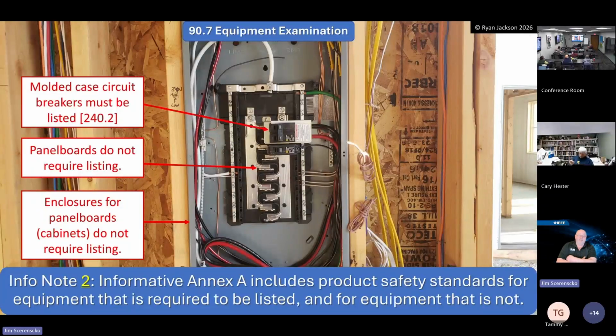And that's a really sore subject because when I did the Falcon Stadium in Atlanta, I was the quality control, quality assurance manager for that building when it was built from the dirt up. The engineers came back and said, well, we don't want to see any of the labels from the EMT. Well, it's an open floor plan building. I mean, you're going to see the conduit. And every stick of conduit has a label on it. It's not only the listing, but it's also the SKU number and the barcode and everything else, because they do sell it a stick at a time in some places. And so they wanted us to go back and peel off all the labels. I said, I ain't doing that. And so the argument was that it had to be listed and labeled, but actually EMT only has to be listed, not labeled. So I don't know if there is a philosophy behind it, but everything that's installed per the NEC shall be listed, not necessarily labeled.